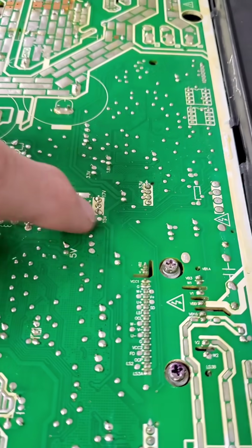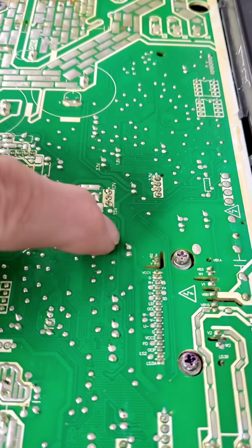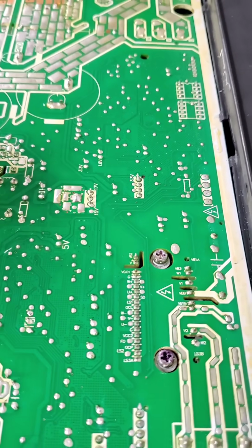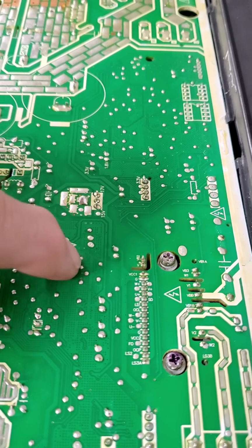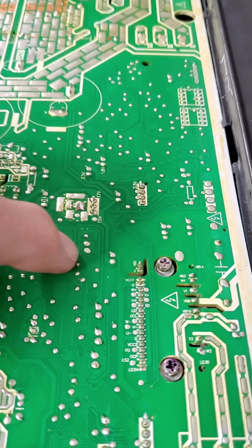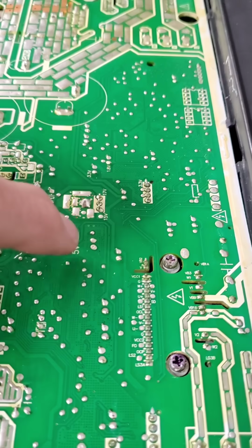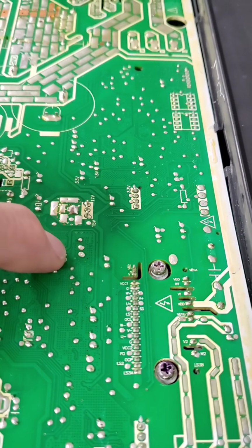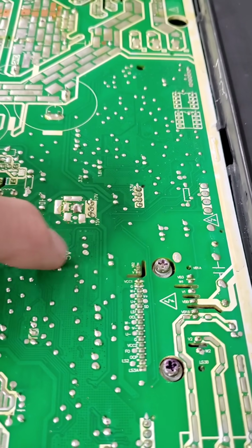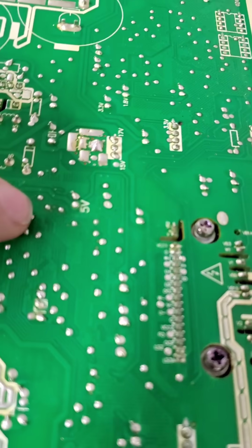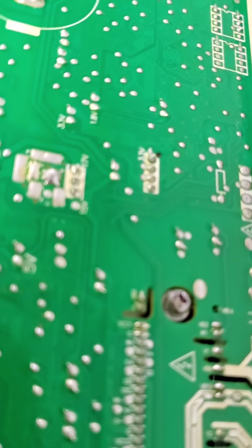Another thing I should touch on is when you're testing this, there's a coating on this board that keeps corrosion and stuff off. So when you test the 5 volts, you might have to scratch just a little bit before you do it. And of course, before you do that, cut the power off. Then cut your power on and test your voltage. But you might can see that little bit of stuff they put on it to keep the corrosion off.